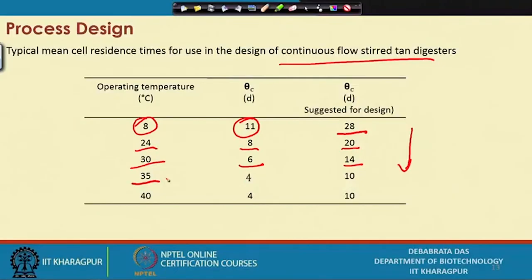If the rate of acid formation is higher than the rate of methane generation, acid concentration in the reactor increases, pH goes down, and the rate of methane formation reduces significantly — this is the major problem. Temperature is also critical: during winter in India, temperatures can drop to 15–20°C. Even though biochemical reactions are exothermic, the temperature will drop, significantly decreasing the rate of reaction.